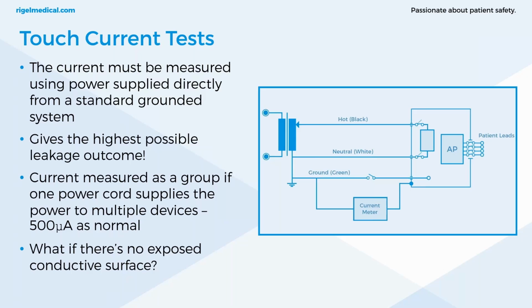And then that part is considered the exposed metal surface of the appliance, and all appropriate tests can be performed using that foil. So that then becomes your exposed conductive surface. That's one way of doing it. Or some people would, if there's a protective paint, scratch off that paintwork and try and get a connection that way. But this is one way of performing that test without causing any damage to the equipment.